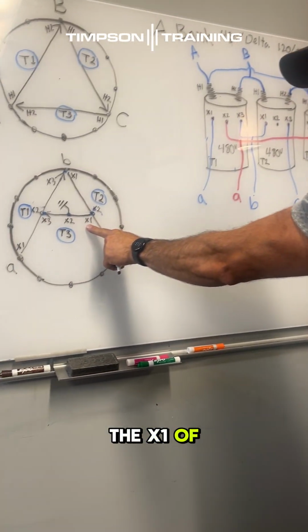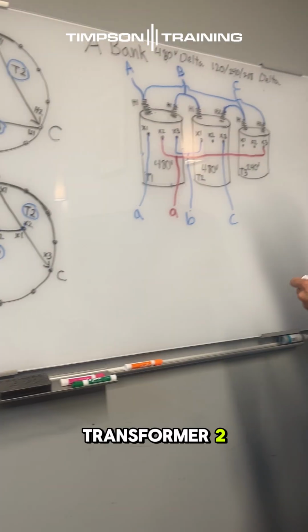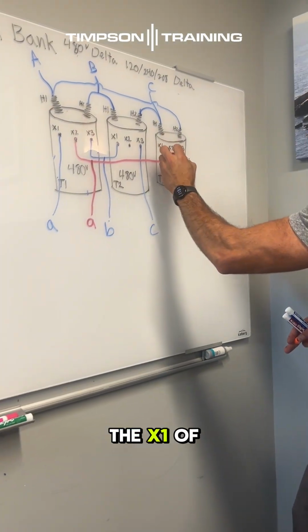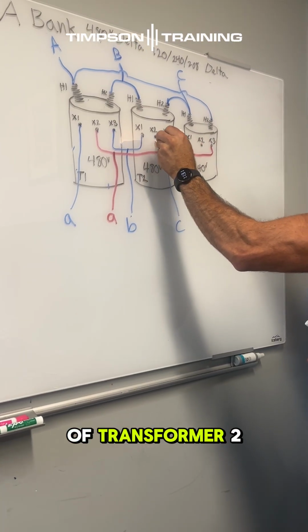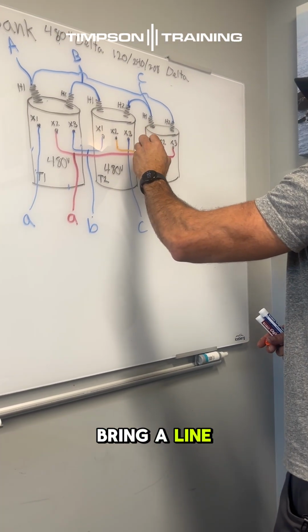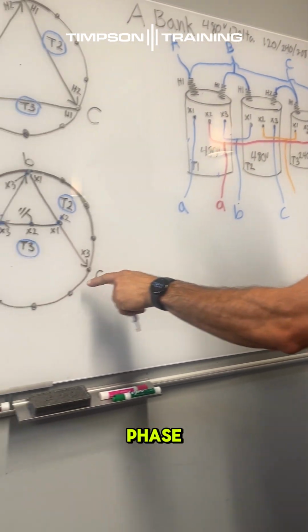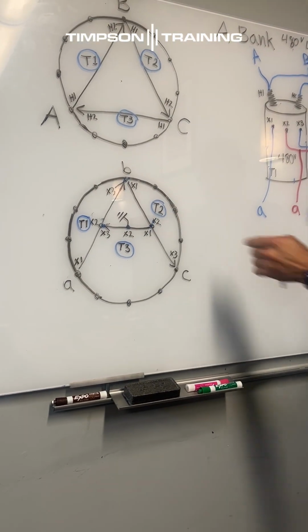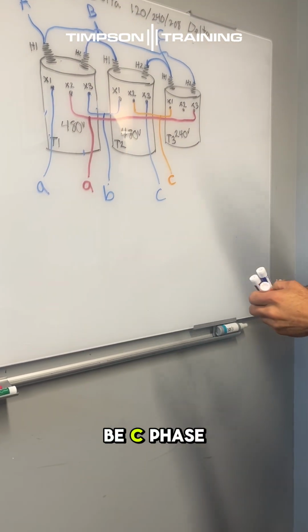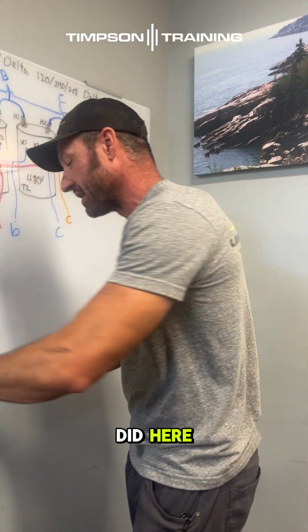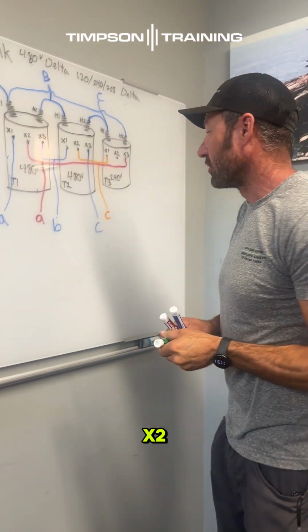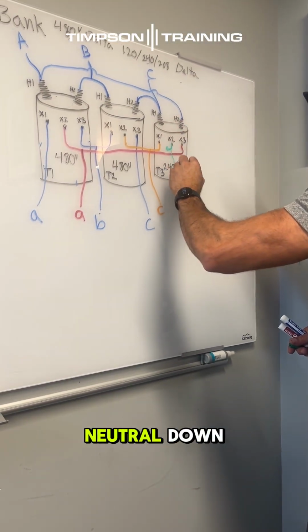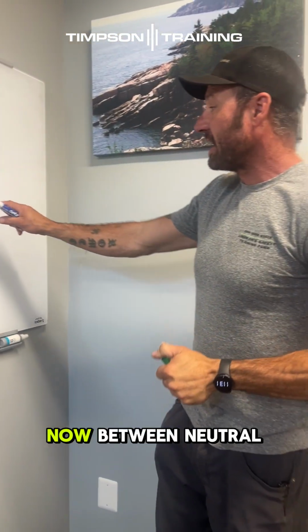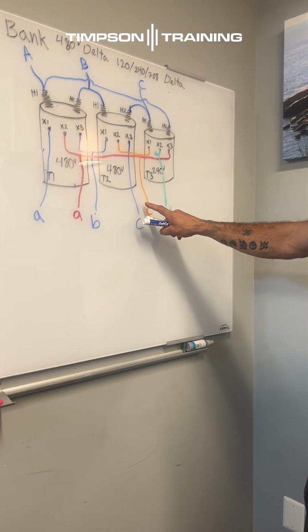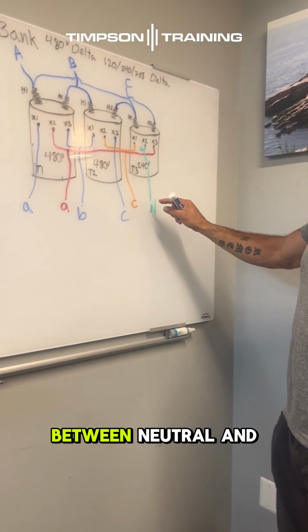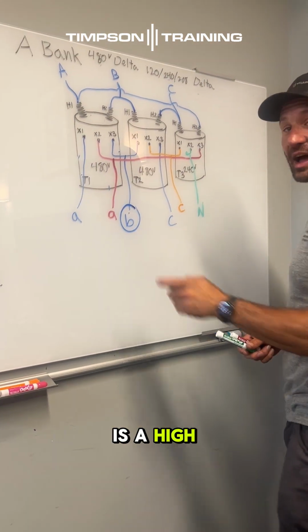The X1 of transformer 3 ties to the X2 of transformer 2. Let's do that one in orange. Now we're going to bring a line down here, and that's also going to be C phase. So we're going to take that phase and slide it right up. That's going to be C phase also, but that's going to be C phase on your 240 volt side. Now you see what else we did here. We grounded the X2. So now we're going to put our ground strap on and run that neutral down. So now we have our neutral down. Between neutral and here, we have 120 volt. Between neutral and our B phase over here is a high leg.